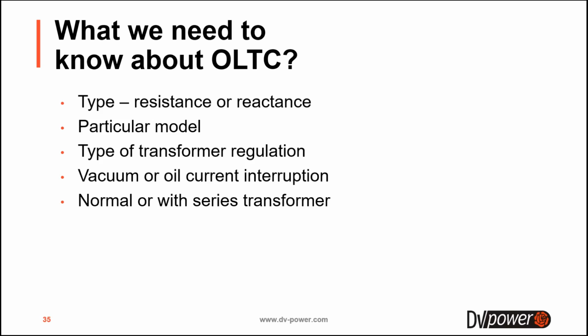Now you need to know the particular model, because different models have, for example, a different number of resistors. We will see later on. So you have models with 1 resistor, 2 resistors, 4 resistors, 6 resistors, and all of those designs influence the DV test graph. You need to know the type of transformer regulation, the type of OLTC regulation. Is it linear, plus-minus, coarse-fine? That also influences the overall graph. You need to know, is it vacuum type or oil current interruption LTC? Is it a normal or regular LTC, or is it with series transformers? LTCs with series transformers are not widely used, but there are some cases when they are used, and it's good to know them.